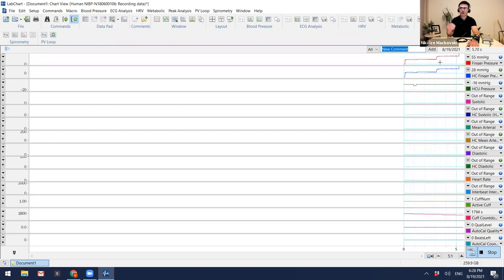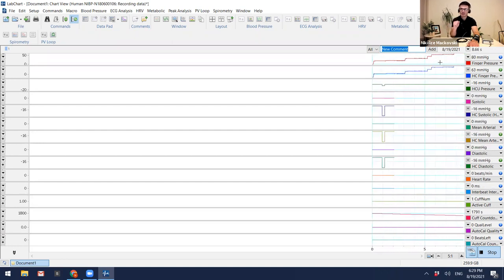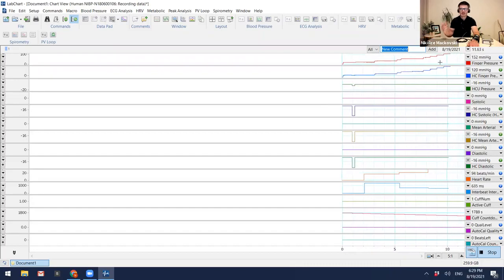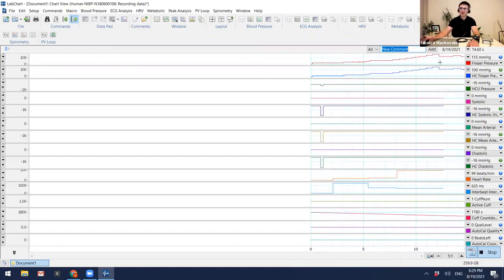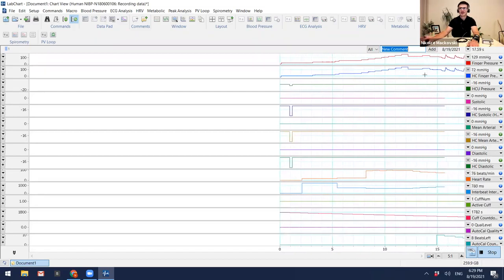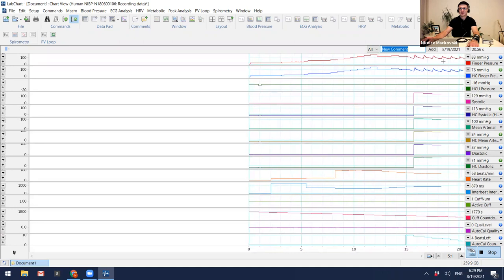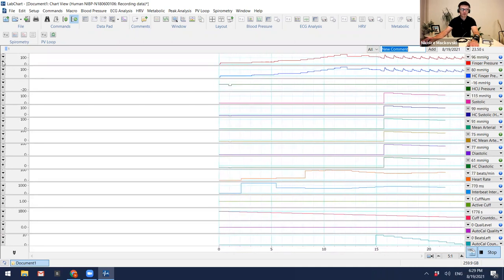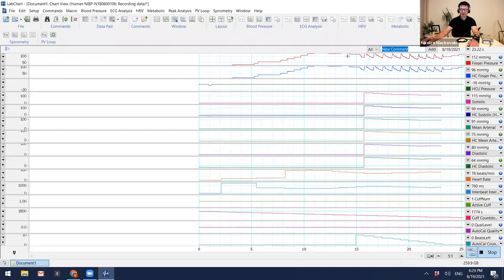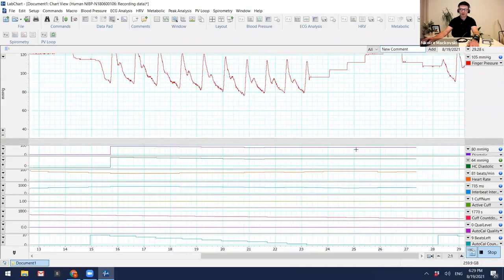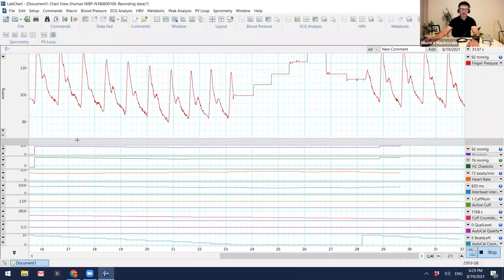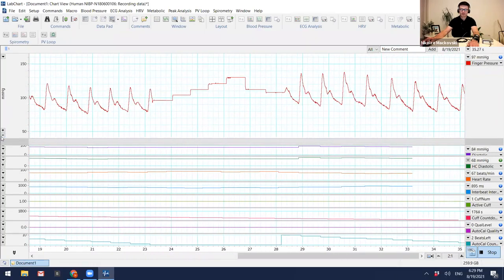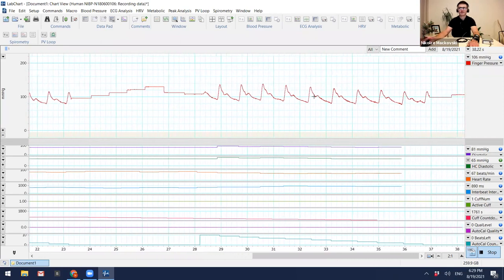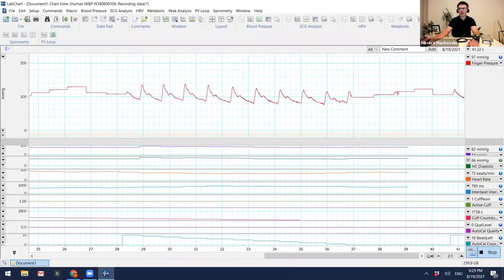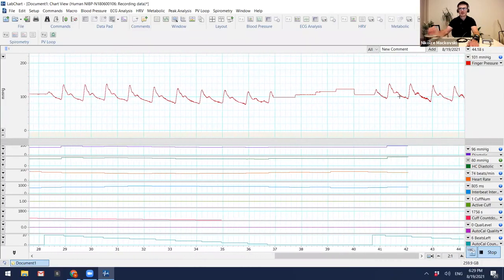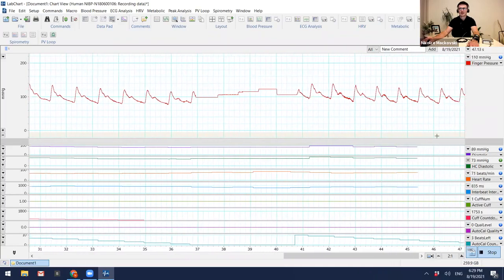You can see now that the pressure, the feeling is that the cuff is increasing obviously in pressure until it reaches above systolic. Once that happens, you can clearly see that we're getting the readings right there. So we're getting 94, 98, you actually see the readings there. If I zoom in a little, like this, you can actually see the readings there. So I can probably zoom out a bit. So that's clearly showing you there the dicrotic notches. It does a couple of levels of calibration points, and now it just continues. So that's a nice and clean signal.